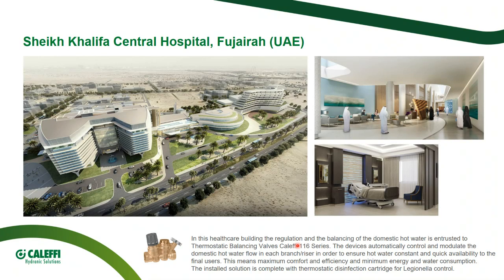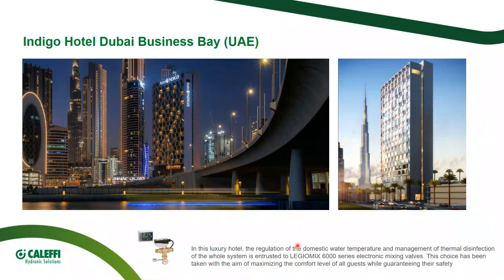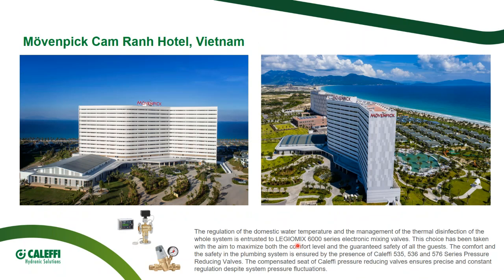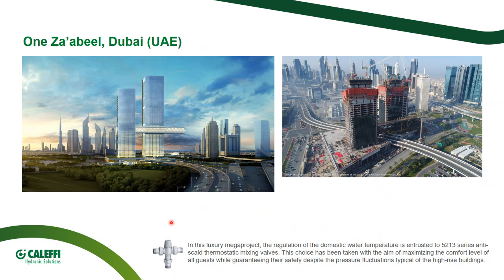If we speak about healthcare, Caleffi supplied thermostatic balancing valves in Fujairah in the Sheikh Khalifa Central Hospital, where the performance of the system is very important as it is a healthcare building. Indigo Hotel Business Bay decided to install digital mixing valves for Legionella control, and some other international hotel chains, like the Movenpick Hotel in Cam Ranh City in Vietnam, decided to equip the system with electronic mixing valves with Legionella treatment and also pressure reducing valves. The last three examples concern the application of a peripheral mixing valve with anti-scald function. One of them is One Za'abeel. The One Za'abeel designers decided to equip the building with anti-scald thermostatic mixing valves with third-party certification in order to ensure safety to the users.